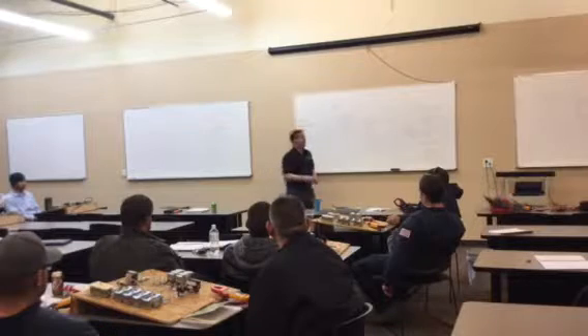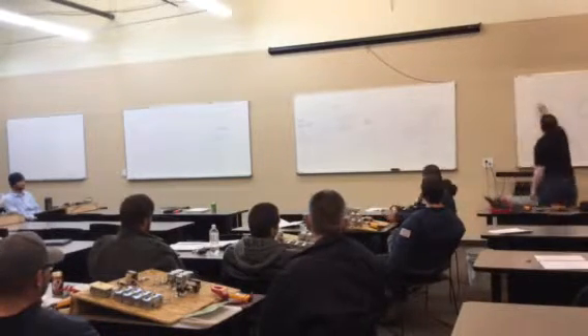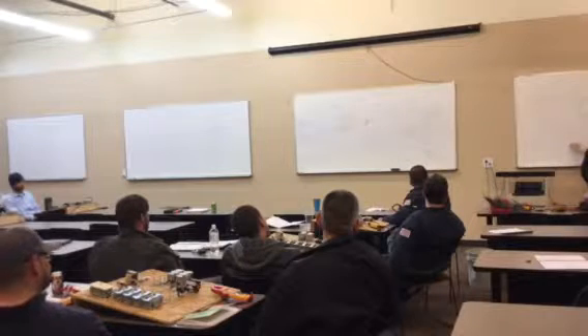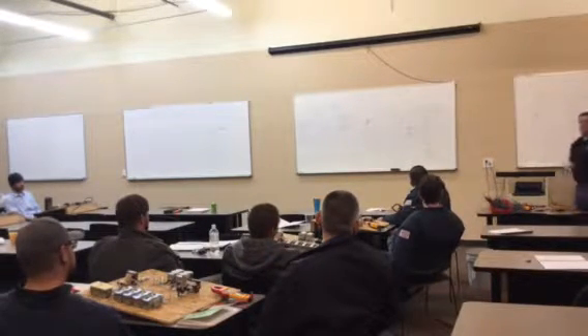Here's how you find that problem. You need 2 meters. If I've got a transformer over here, and I've got a gas valve over here, I want to have 1 meter monitoring the gas valve voltage, and another meter measuring the transformer output voltage.